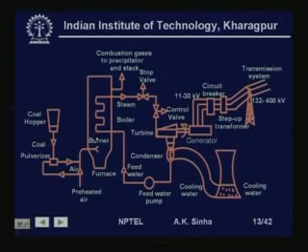of the burning of this coal creates the flue gases, and these flue gases are very hot and they heat up the water tubes in the boiler, and the water in the water tubes will get heated and become steam. Of course, of this very hot flue gas most of its heat is taken away here, but still the hot flue gases are to be removed, and this is done by means of the stack, the large chimneys that you see in some of the thermal power plants.